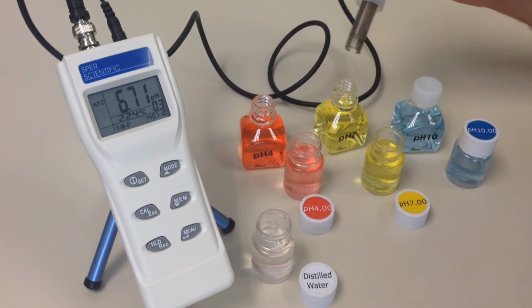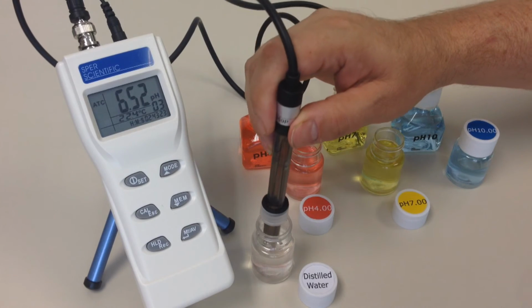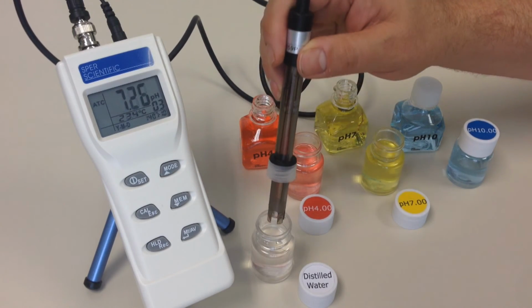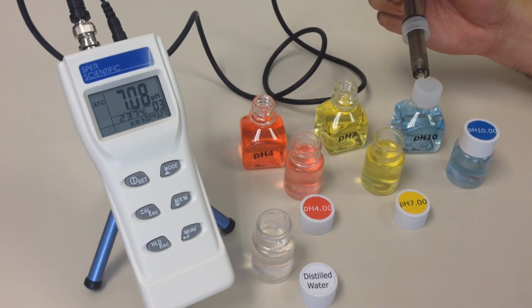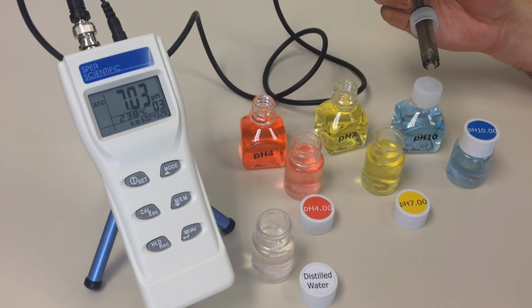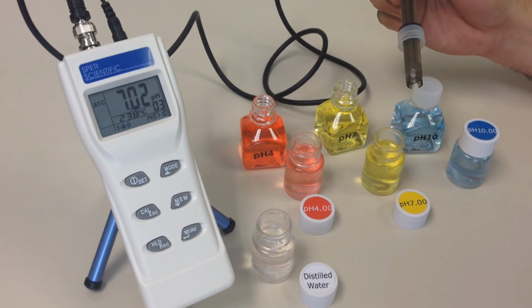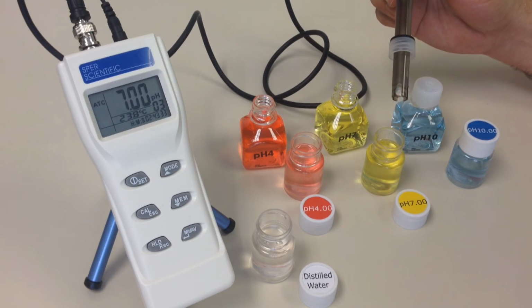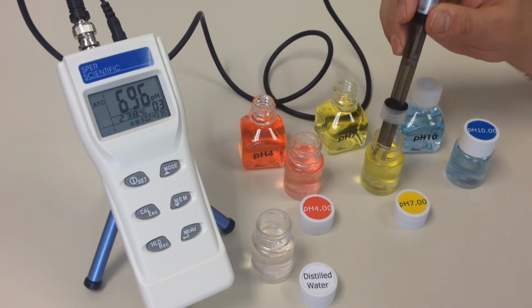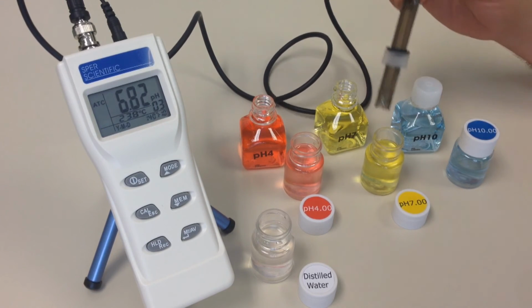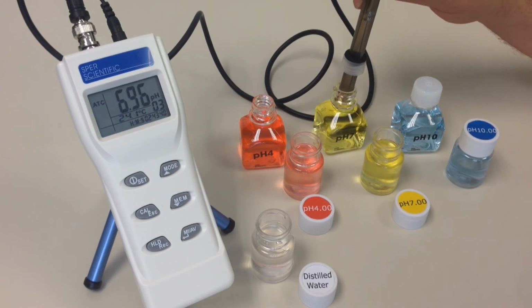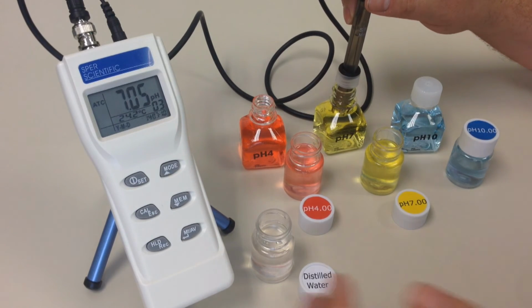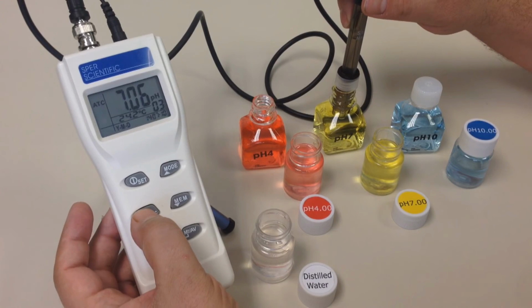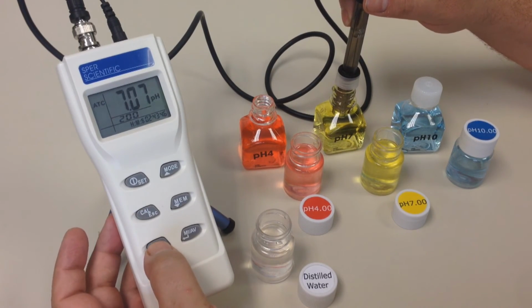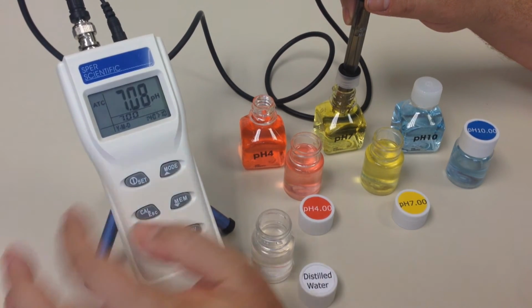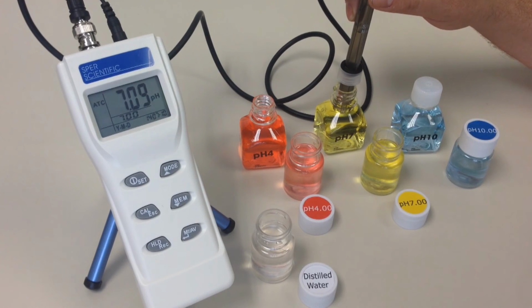So again, the first thing I'm going to do is clean off my probe using a little distilled water. And in this example, I'm using best practices, so I have 2 bottles of pH 7 open and 2 bottles of pH 4 open, so I don't contaminate the actual solution I'm going to be testing. So I'm going to take the probe, put in a little pH 7. Now I'm going to put it in my secondary bottle, or the bottle I'm actually going to be calibrating to. So all I do is hit Cal, hit the hold or C button until on the secondary screen 7.0 appears.